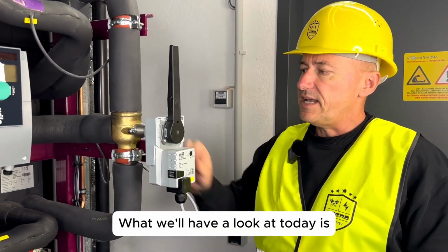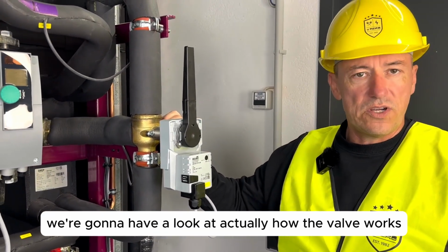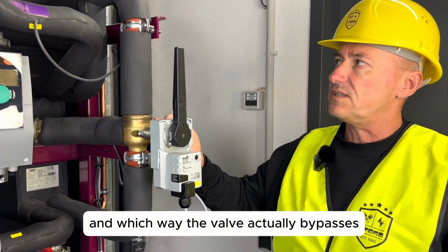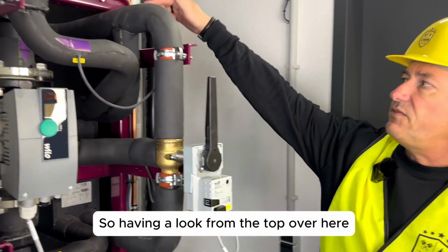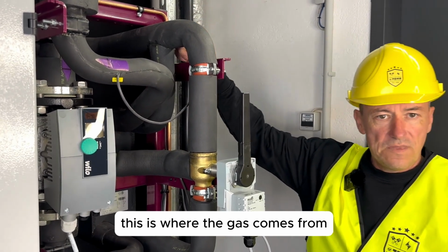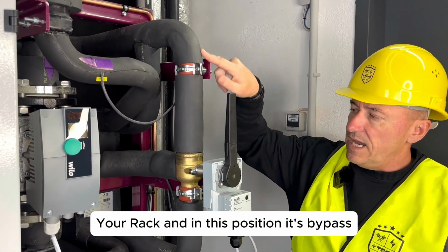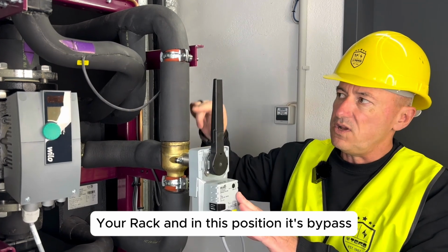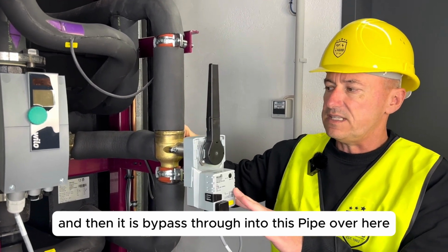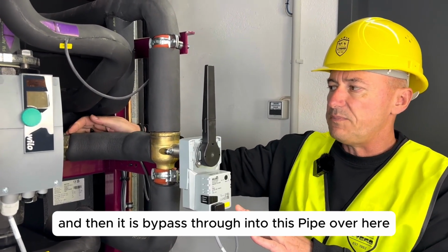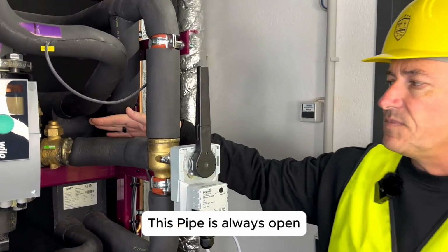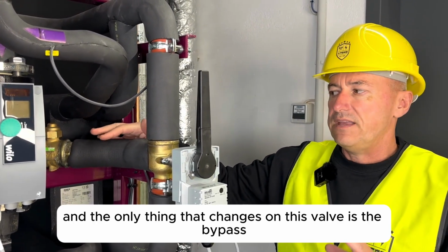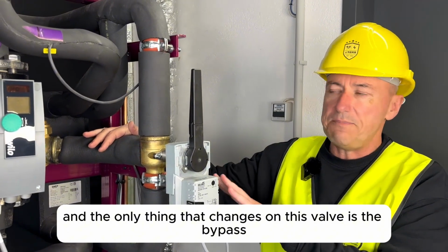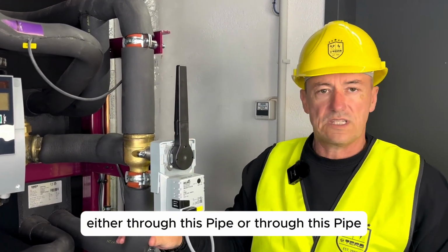What we'll have a look at today is actually how the valve works and which way the valve bypasses. So having a look from the top over here, this is where the gas comes from your rack, and in this position it's bypassed, so the gas is coming down here and then it is bypassed through into this pipe over here which goes to the gas cooler. This pipe is always open and the only thing that changes on this valve is the bypass either through this pipe or through this pipe.